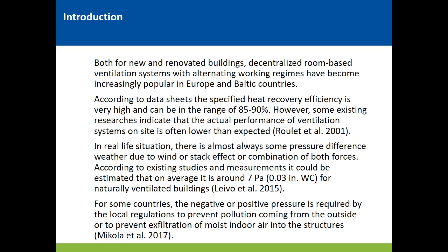At the beginning, a small introduction. As you know, for all new and renovated buildings, there should be some kind of ventilation system to keep the indoor air quality good and the environment healthy for the persons living in it. There are many types of ventilation systems available on the market. For example, large, full mechanical ventilation systems, or maybe just some exhaust in bathrooms or kitchens. But sometimes you need the possibility to recover the heat from the exhaust air to the supply air to keep the energy consumption as low as possible, as the energy lost by ventilation can actually be more than half of all the energy loss of buildings, especially in northern climates.